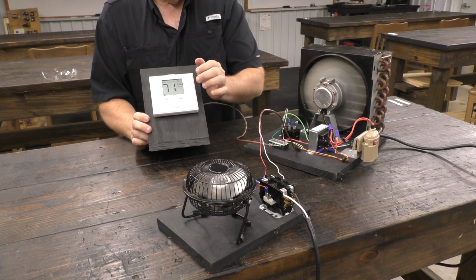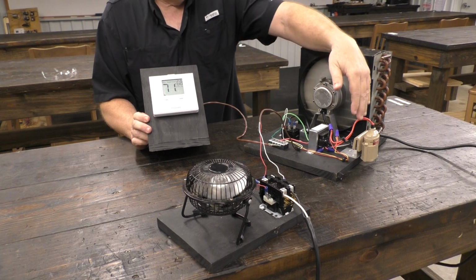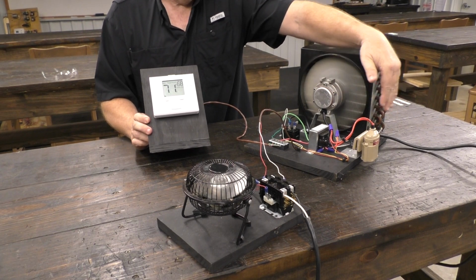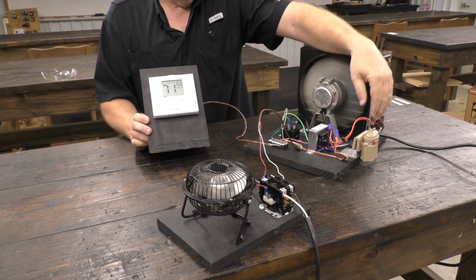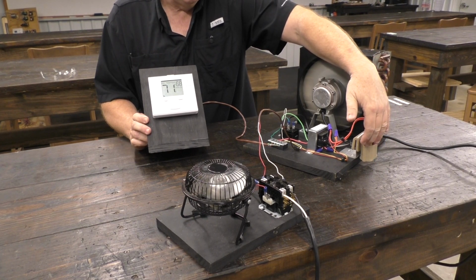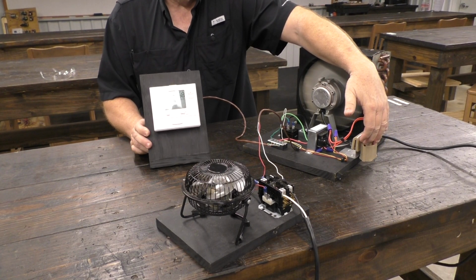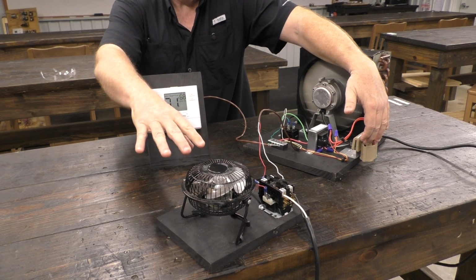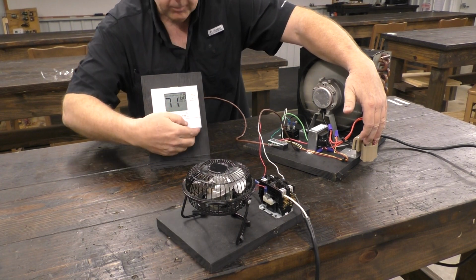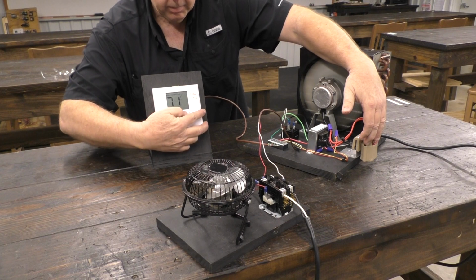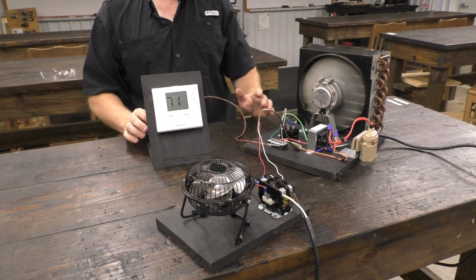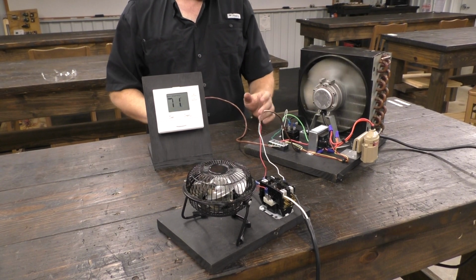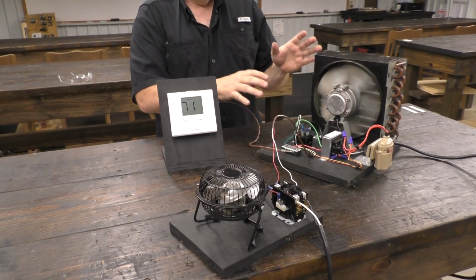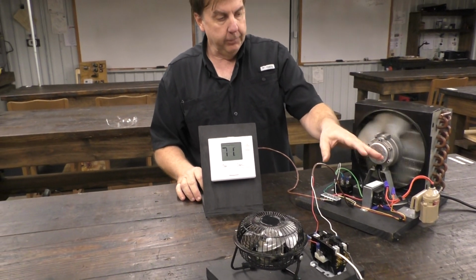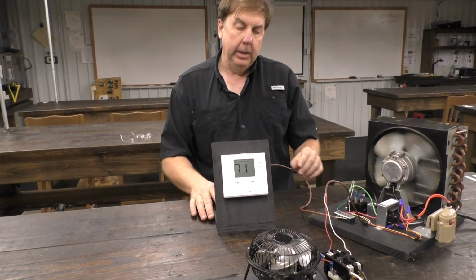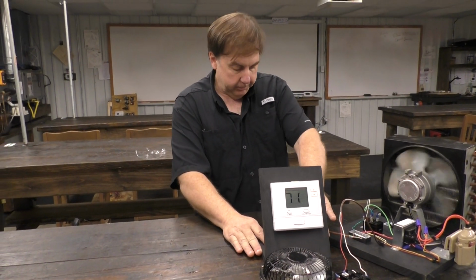If we had a problem in this house and started getting water in our float, in our drain pan, before it got into our ceiling, the float switch would raise up. As you can see, the indoor fan kept running, but the outside unit went off. When that outside unit turns off, I stop making water. Even though the fan's still running inside, we're no longer making water. So the float switch did its job, turning off the outside unit so we didn't have damage.